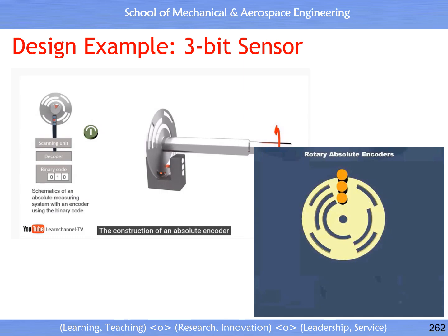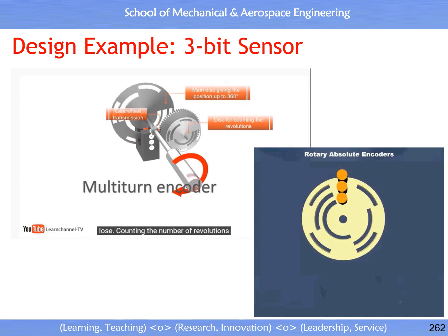The construction of an absolute encoder is more complex compared to an incremental encoder, as they require a decoder. But the big advantage is that each angular position of the shaft can be read at any time, even after a power failure. That means there is no counter value to lose. Counting the number of revolutions with a multi-turn absolute encoder. This example shows a two-stage multi-turn encoder.